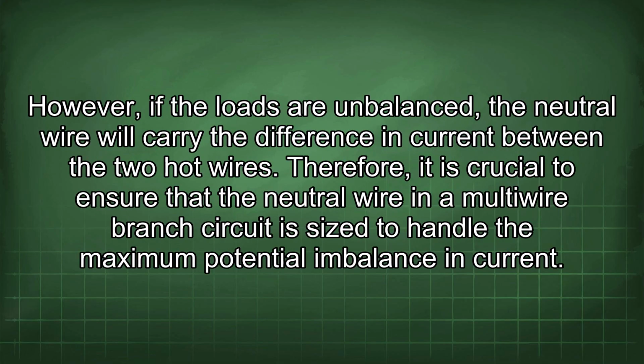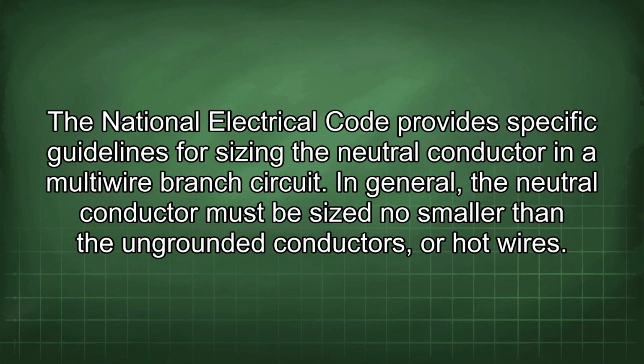However, if the loads are unbalanced, the neutral wire will carry the difference in current between the two hot wires. Therefore, it is crucial to ensure that the neutral wire in a multi-wire branch circuit is sized to handle the maximum potential imbalance in current. The National Electrical Code provides specific guidelines for sizing the neutral conductor in a multi-wire branch circuit. In general, the neutral conductor must be sized no smaller than the ungrounded conductors or hot wires.